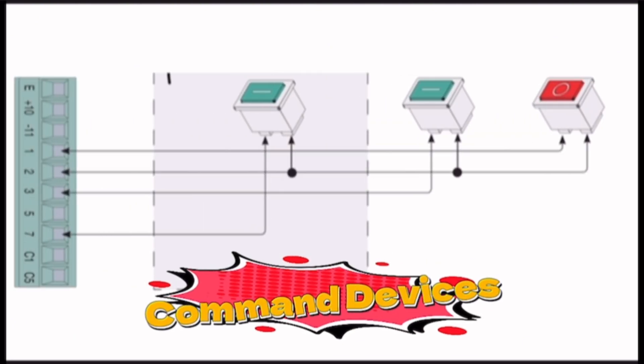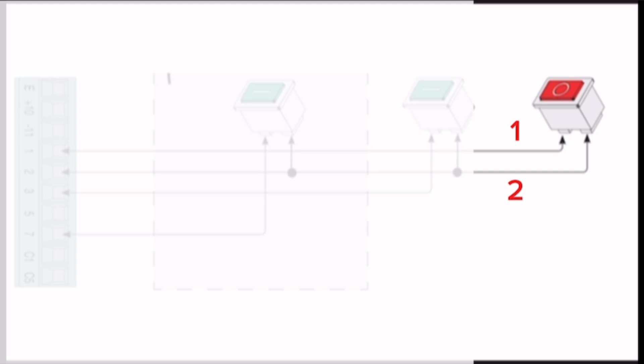Command Devices: Terminal 1 and 2 is stop button NC contact. Button to stop barrier arm. To resume movement, press the command button or transmitter key. If unused, set DIP switch 9 to ON.